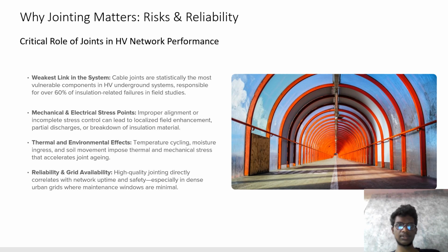Why jointing matters: risk and reliability. Critical role of joints in HV network performance. Weakest link in the system: cable joints are statistically the most vulnerable component in HV underground systems, responsible for over 60% of insulation-related failures in field studies. Mechanical and electrical stress points: improper alignment or incomplete stress control can lead to localized field enhancement, partial discharge, or breakdown of insulation material. Thermal and environmental effects: temperature cycling, moisture ingress, and soil movement impose thermal and mechanical stress and accelerate joint aging. Reliability and grid availability: high quality jointing directly correlates with network uptime and safety, especially in dense urban grids where maintenance windows are minimal.